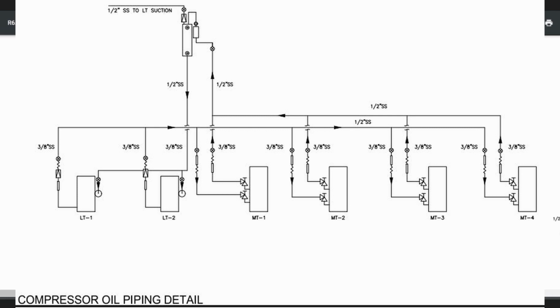There you go, right up there. And then the oil reservoir is vented at a 10-pound check valve to the low temp section. So it's running about 2 or 3 pounds. You got 25 pounds on the crankcase of the medium temp. So the oil flows, if there's any oil at half a sight glass, it flows into the reservoir. If there's no oil in the medium temp, then you're just blowing a little vapor over into the low side.